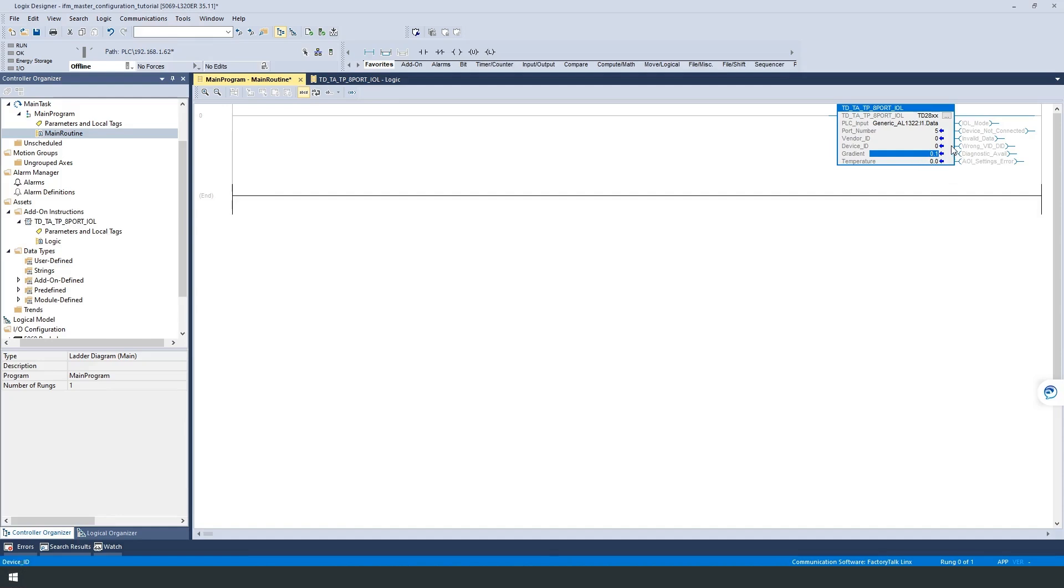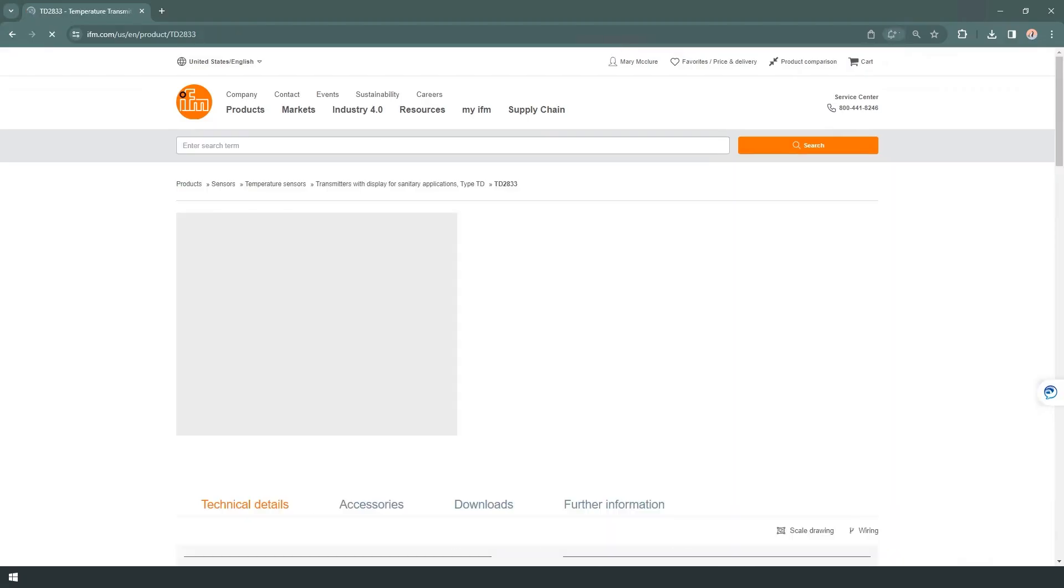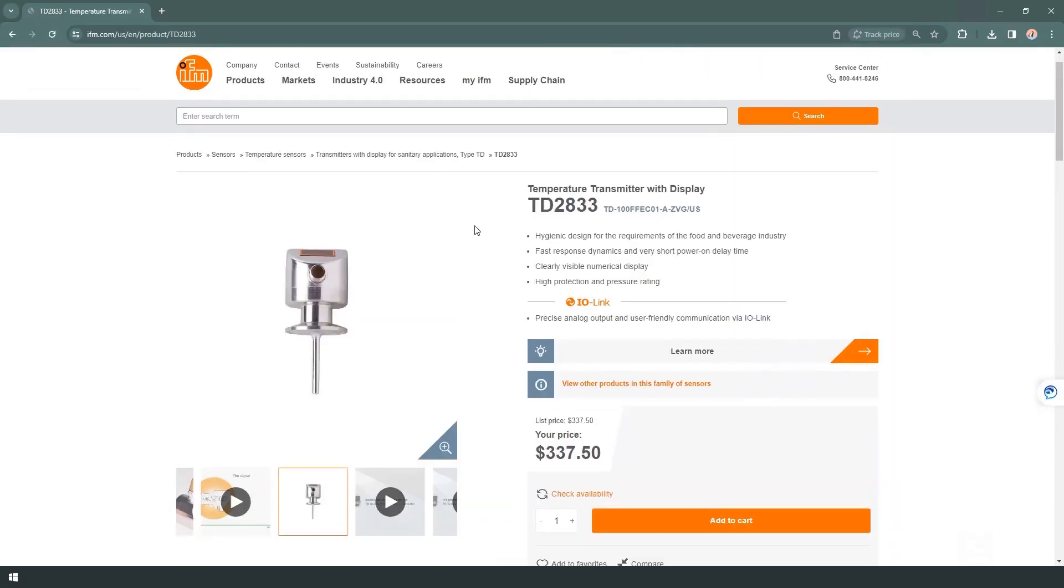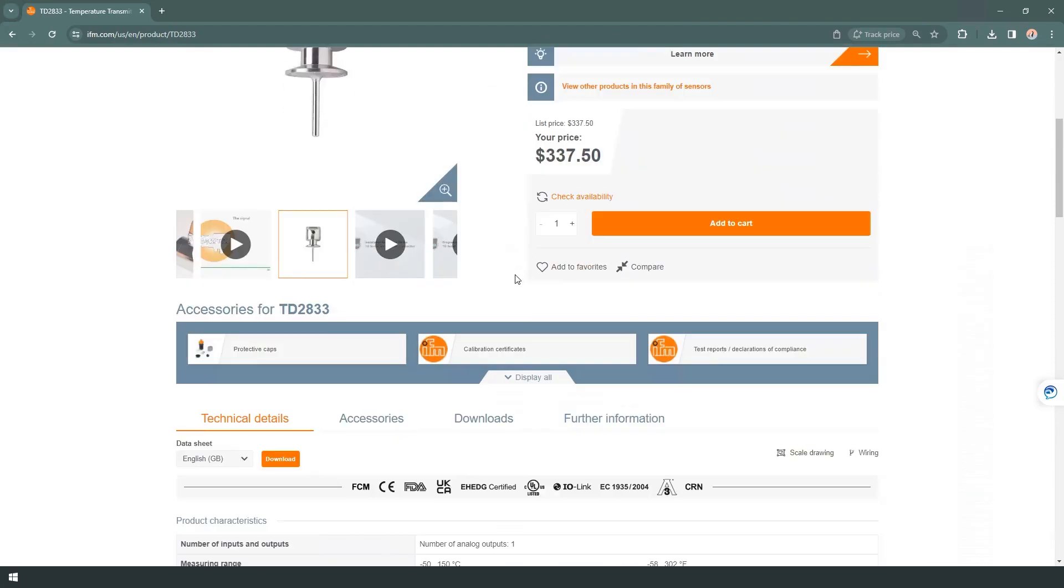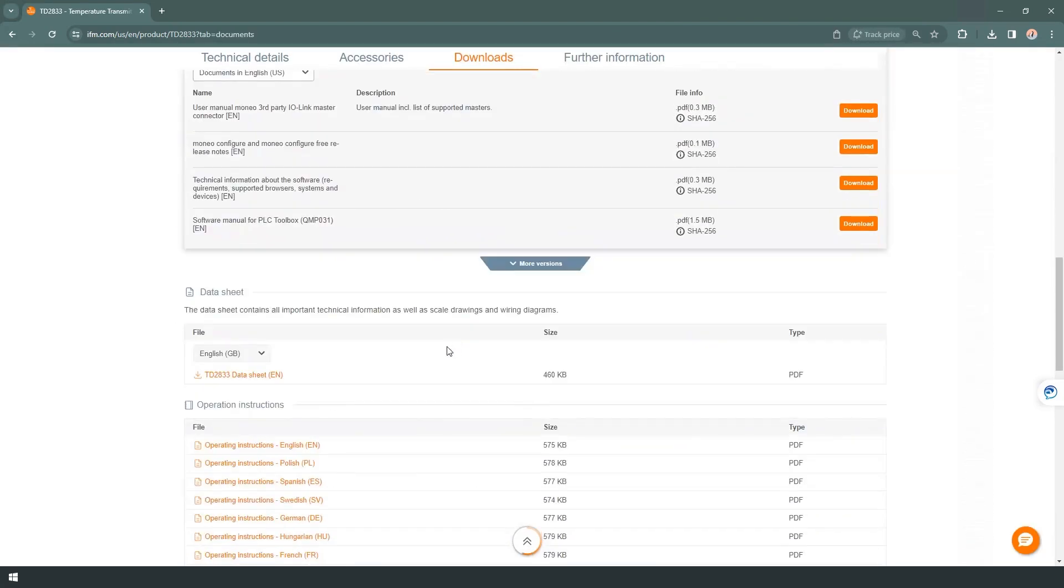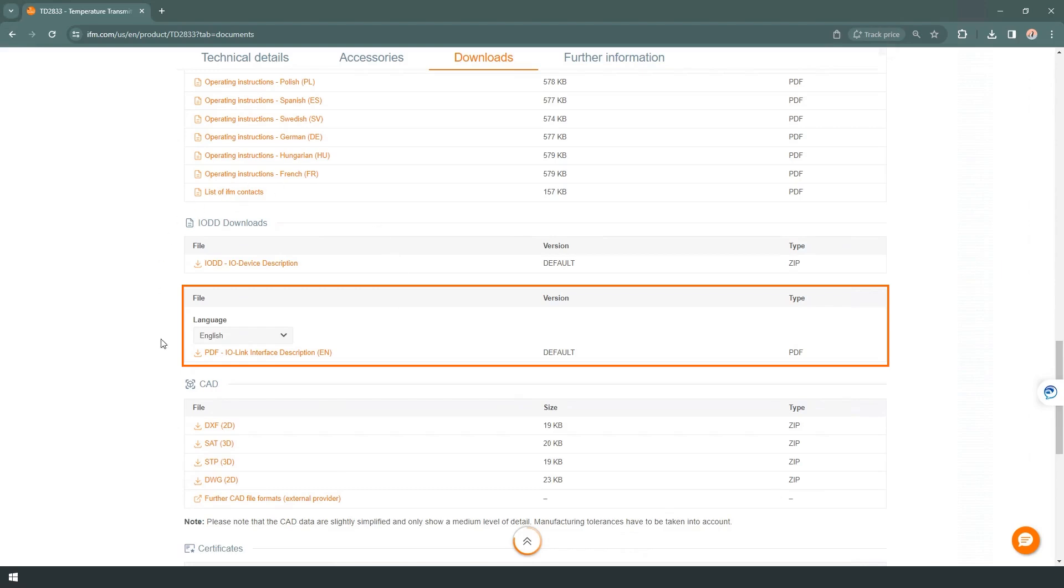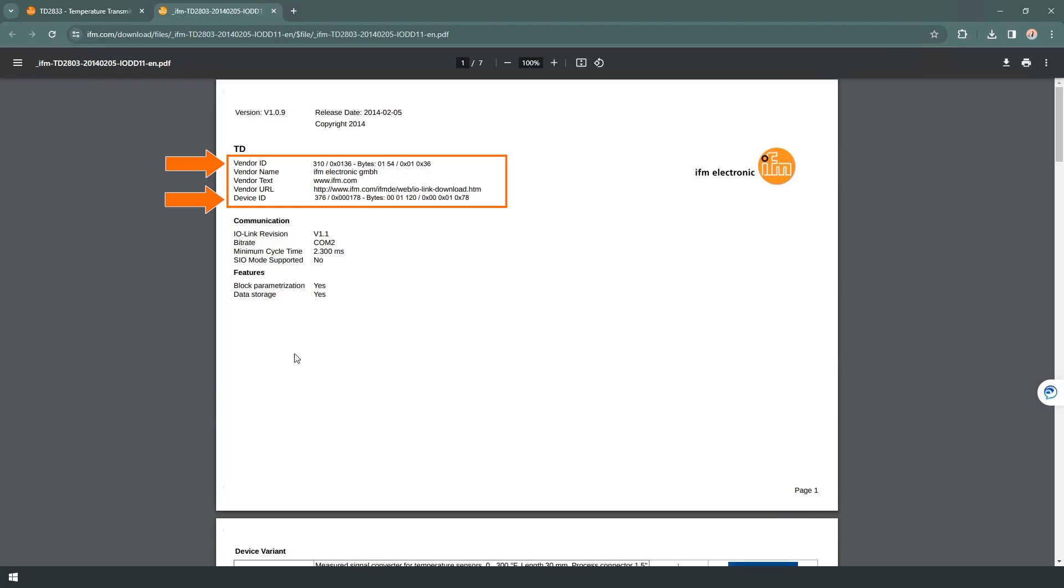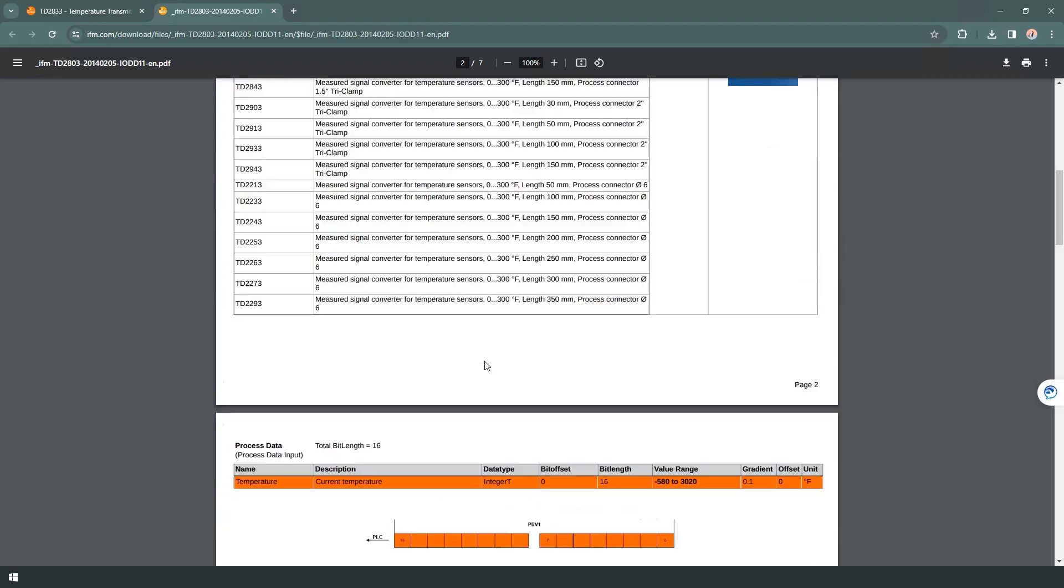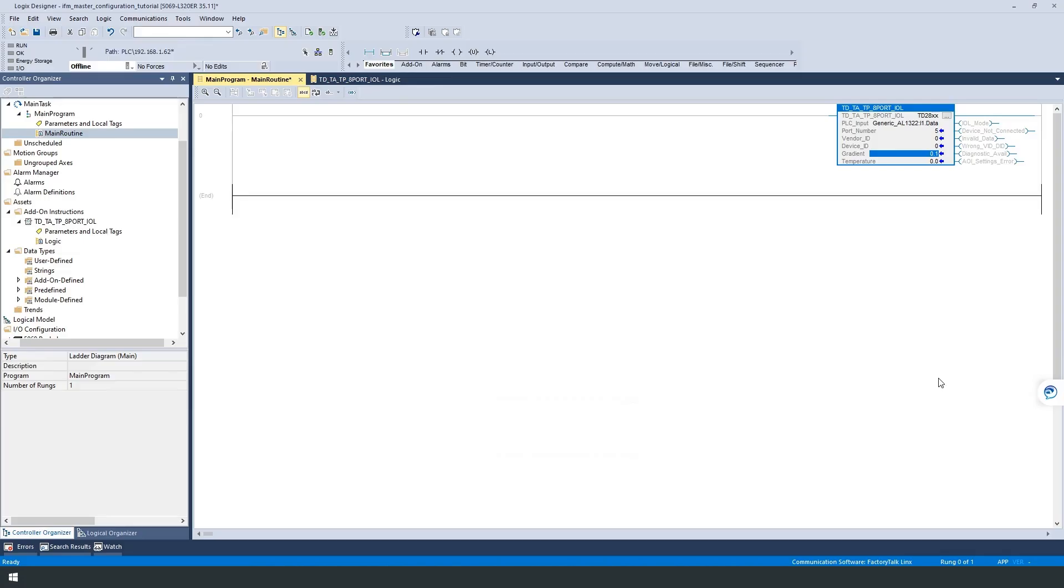This information can be found in the IO-DD PDF of the sensor. This file can be found in the download area of the TD-2833 on the IFM homepage. Scroll down and open the IO-Link device description, or short, IO-DD. On page number 1, you will find general information such as the vendor and device ID. 310 is the vendor ID for IFM, and 376 is the device ID for the TD-2833 temperature sensor we use. This document also contains information on the process data structure of the sensor and the gradient we need. In our case, this is already the default value.